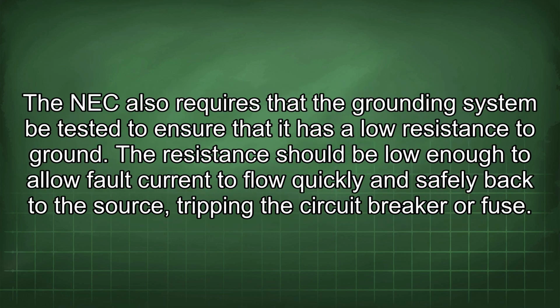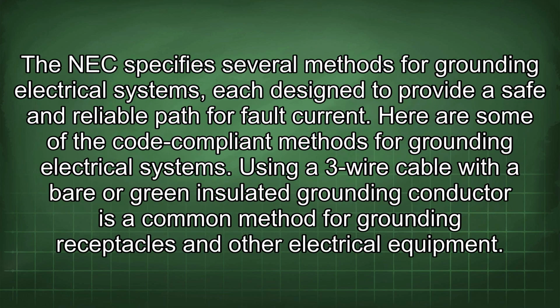The NEC also requires that the grounding system be tested to ensure that it has a low resistance to ground. The resistance should be low enough to allow fault current to flow quickly and safely back to the source, tripping the circuit breaker or fuse. The NEC specifies several methods for grounding electrical systems, each designed to provide a safe and reliable path for fault current. Here are some of the code-compliant methods for grounding electrical systems.